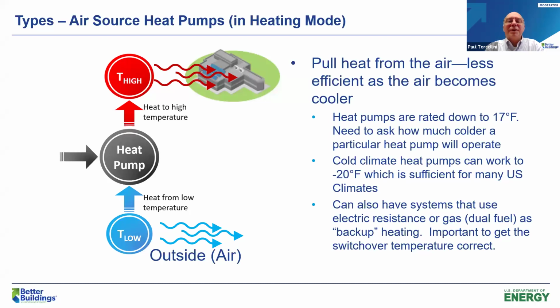We also have systems that are what we call dual fuel. So they use a heat pump for some of the more moderate temperatures and then switch to some kind of backup mode, could be electric resistance or gas as the backup heating. It's important to get that switchover correct. I see a lot of these heat pumps, and we'll hear a bit about it later, where that switchover temperature is really warm and the heat pump isn't working to its full capabilities. So next slide.